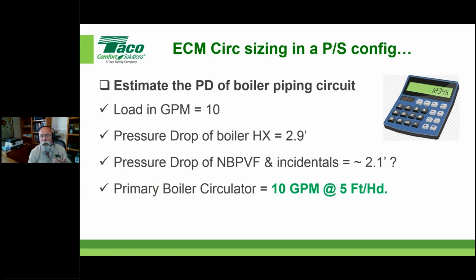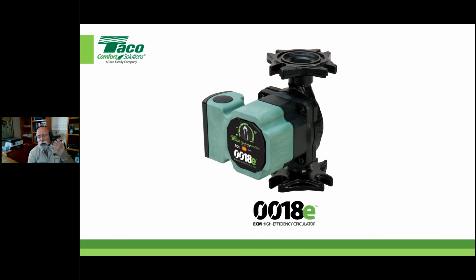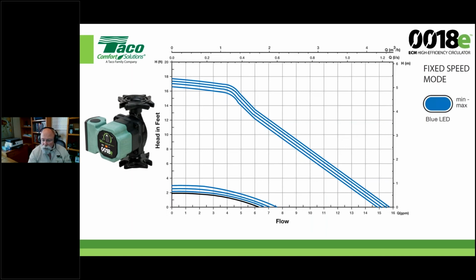Okay. So in this case, I've got a primary boiler circulator with a requirement of 10 gallons a minute at 5 foot of head. Voila. I have the ability to come up with a circulator and make sure it's the right one for the job. Of course, I'm putting my best foot forward here with our 0018E for one specific reason. And again, just like I said, this doesn't have 0 to 10 or pulse width modulation yet. But what I can do with this, as I mentioned early on, is appropriately set the GPM of this pump to what's correct for that specific application that you happen to be working on. Remember, with the fixed speed mode of this pump we can turn it up or down anywhere between 4 watts and 44 watts.